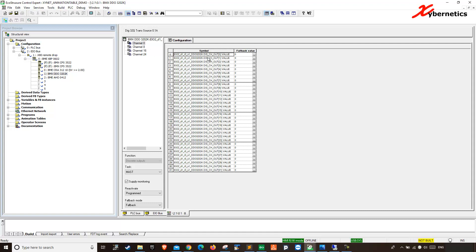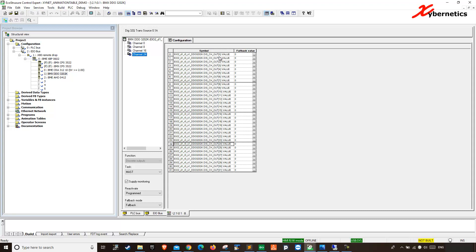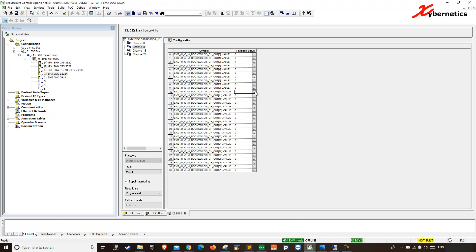The channel 128. See how it highlights different channels all together. So as you can see this column here, fallbacks. Right now everything is set to fallback to zero. If a plant goes down, it comes up again, your DO for every channel will push to zero. You can actually change it to one and customize each different output how they behave. So that's your fallback if the power goes down and comes back on again.